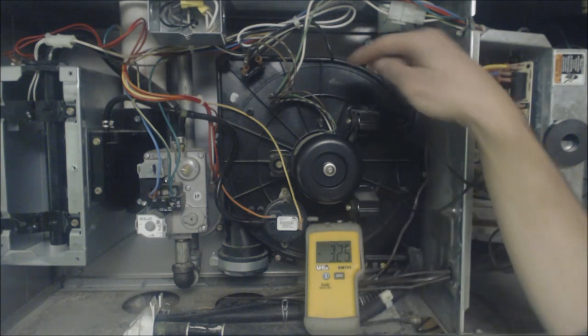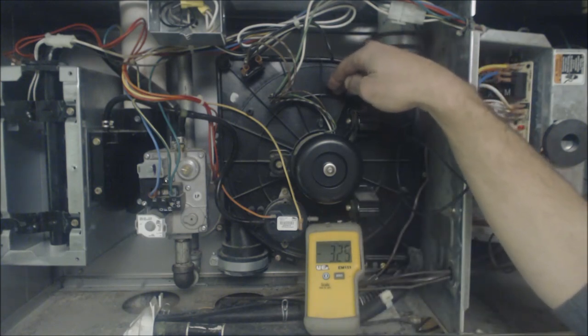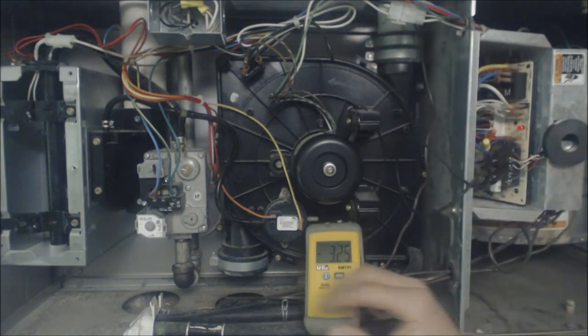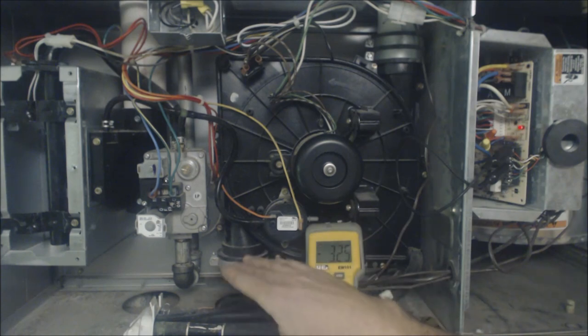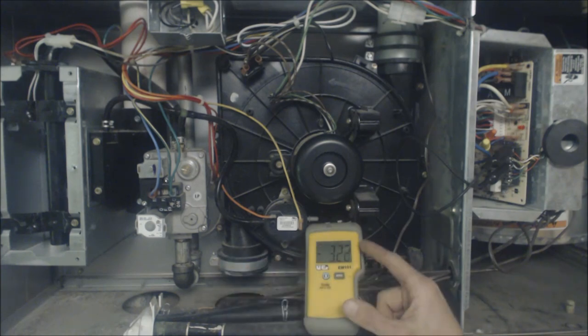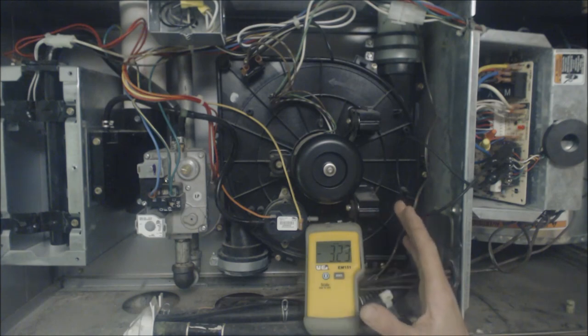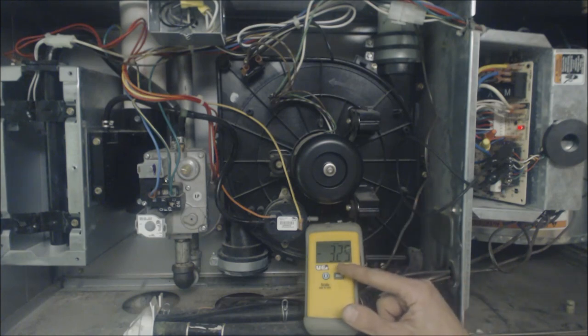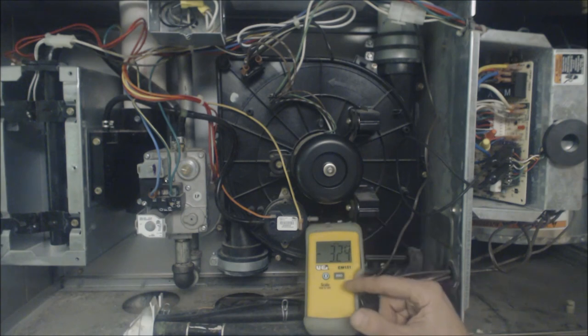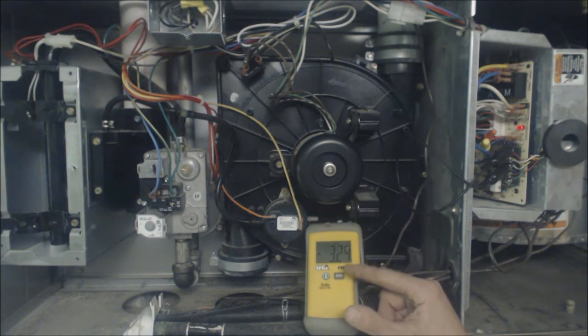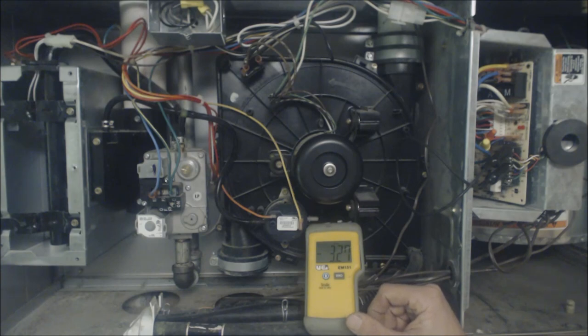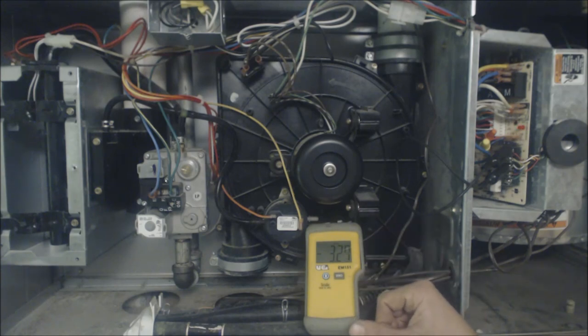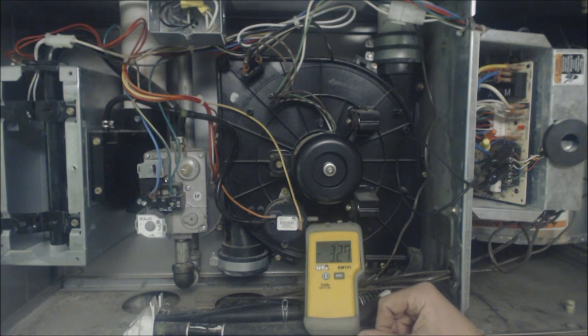The exhaust pipe could be clogged, the blower motor wheel might be broken, you know, this screen could be clogged. But right now we're reading a proper water column reading so everything is fine on this. If you're reading if you're only reading 0.2 or 0.3 or something like that inch water column, then you have a problem, okay, and you need to then figure out what that problem is.